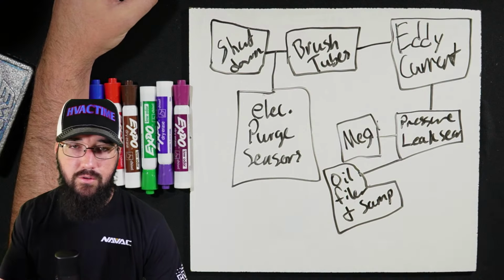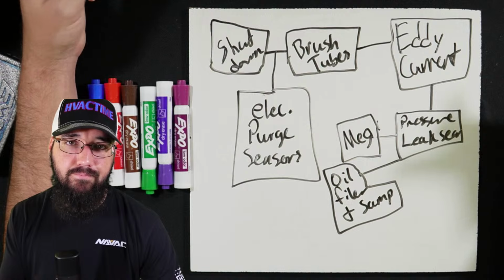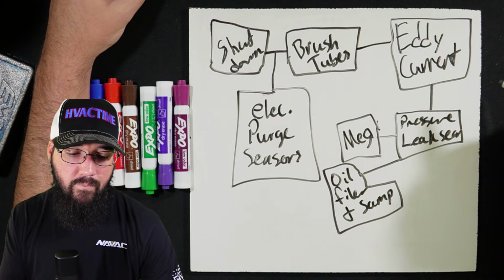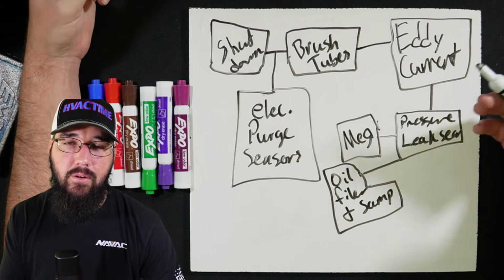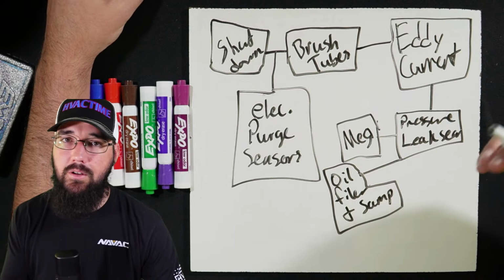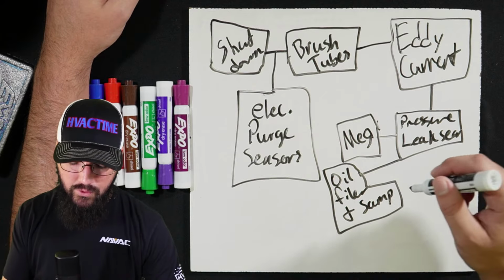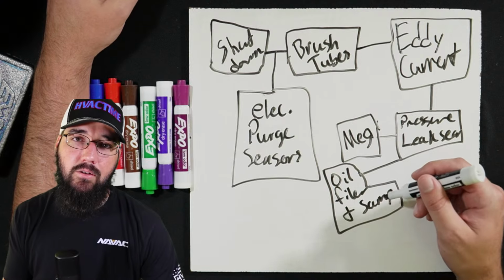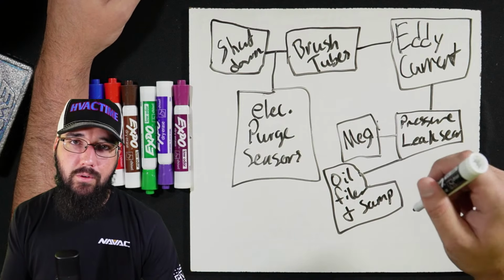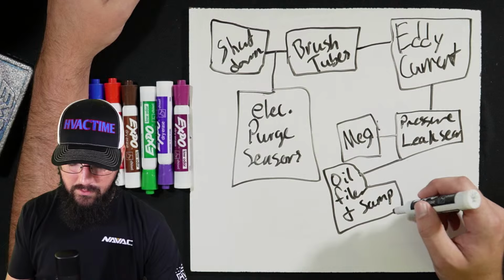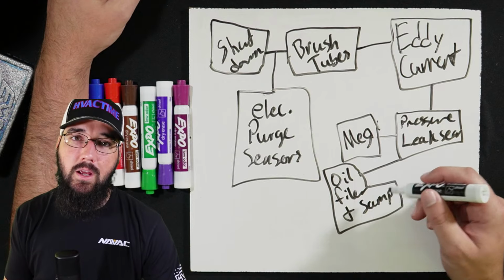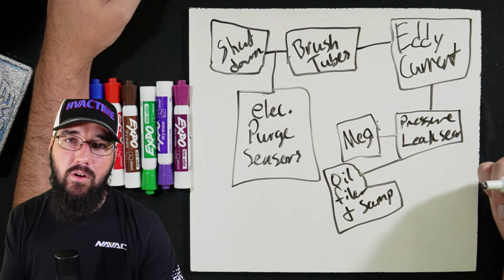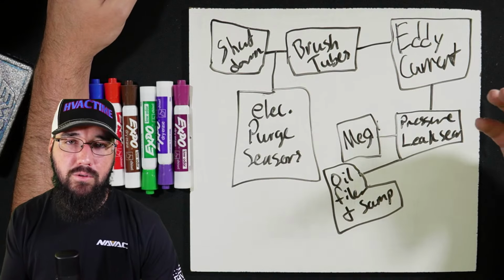service, you're just going to have to deal with the non-condensables getting drawn in. It just is what it is. Usually I'll turn the pump on, and this is one issue with this method. To get your oil sample, you're taking it from the output of the pump, which is not ideal.